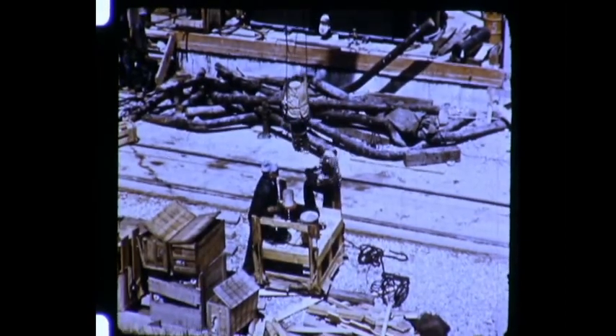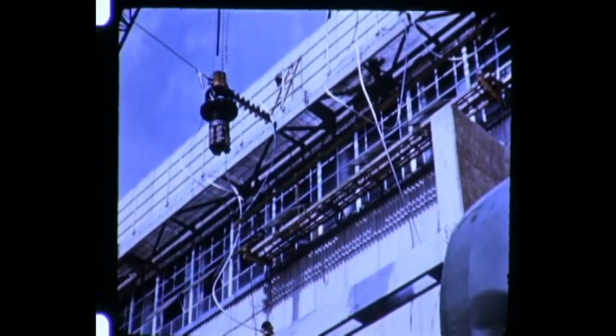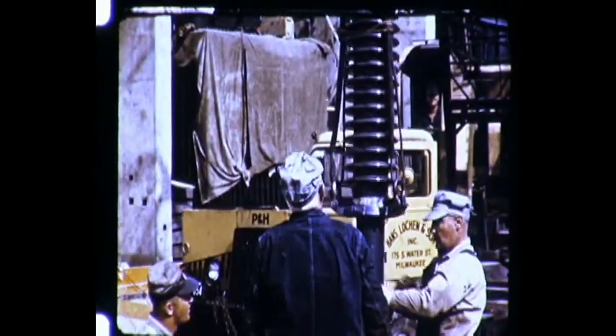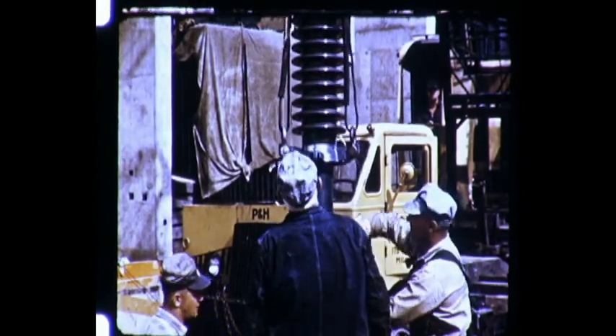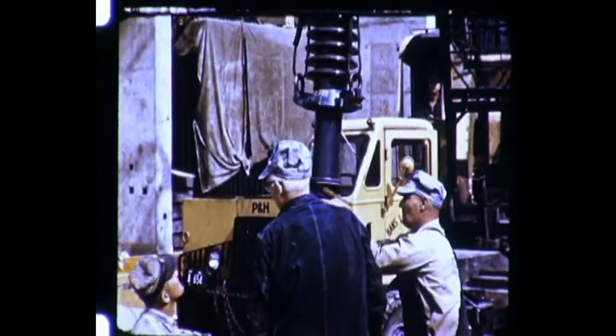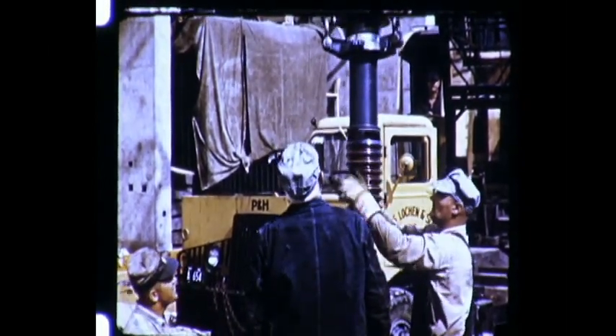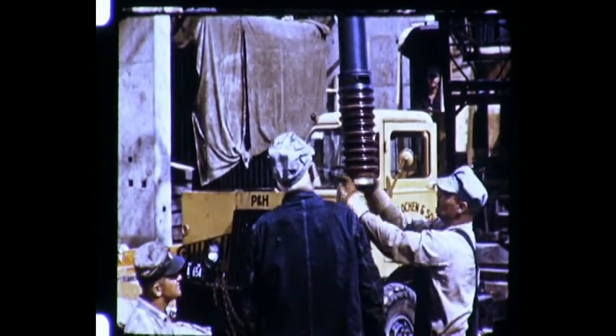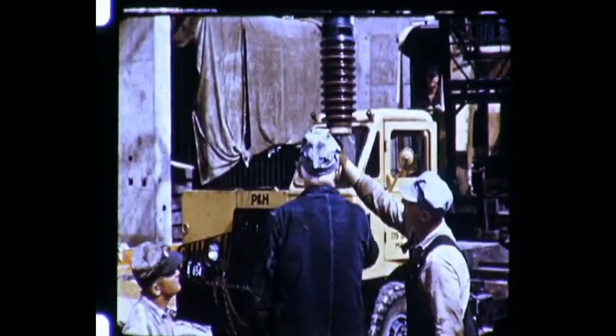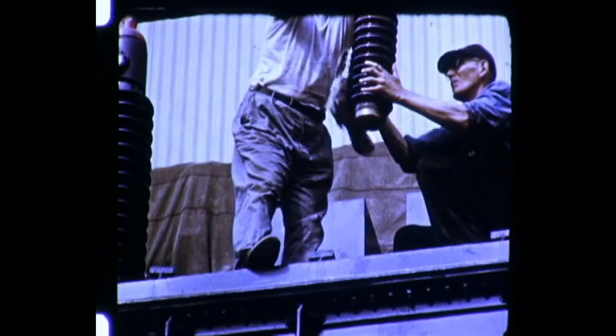At the Oak Creek station, the low-voltage bushings are installed first. These GE high-current bushings, rated 7,000 amperes, eliminate the need for more than one low-voltage bushing per phase. Now, let's get the high-voltage bushings into place. The high side of the transformer, by the way, will deliver 132 kV from generator voltage of 13.8 kV.